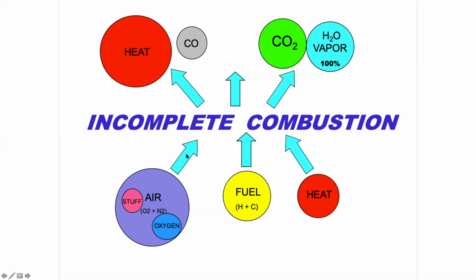As you move through, now you still get the CO2, the water vapor, and heat, but if you don't burn to completion, you'll also get CO. That means that the carbon could not find and merge with 2 oxygens. It only found 1, so it produces carbon monoxide, and mono means 1. So in incomplete combustion, you can develop carbon monoxide. And we'll talk about what causes incomplete combustion in a couple minutes. You can also have excess air, just that extra air moving through the system. And sometimes there's even excess oxygen and just the nitrogen part of the air moving through the system.